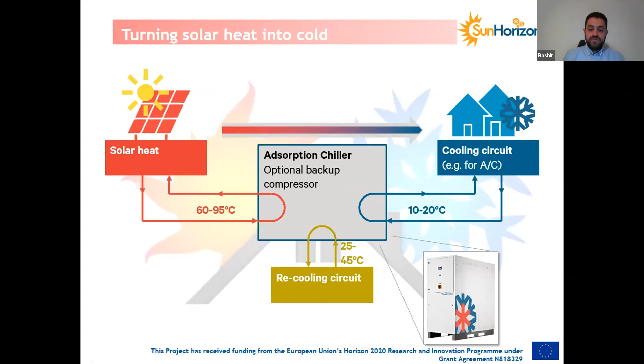Now, the capacity of adsorption depends on all three temperatures in the circuits. The higher the hot water temperature, the higher the capacity. The same with the chilled water circuit: the higher the chilled water temperature, the higher the capacity. But on the other hand, for the recooling circuit, the higher the temperature, the lower the capacity. So when we use dry recoolers, the capacity of the adsorption chiller will depend on the outside temperature.